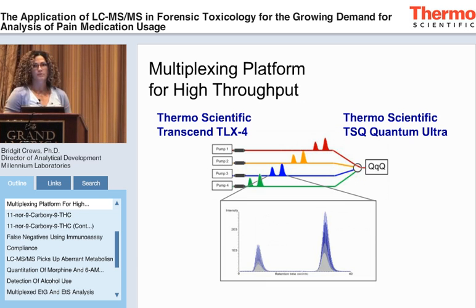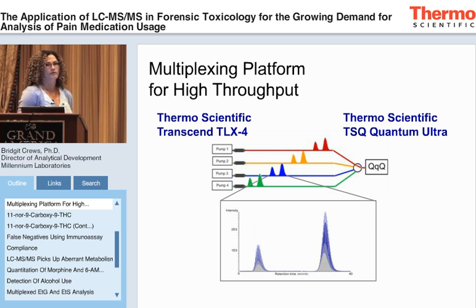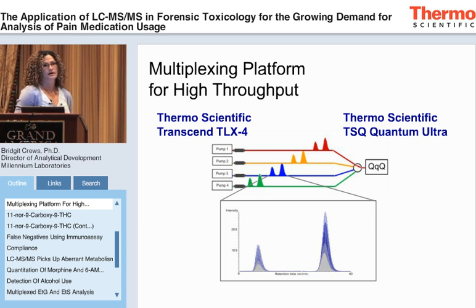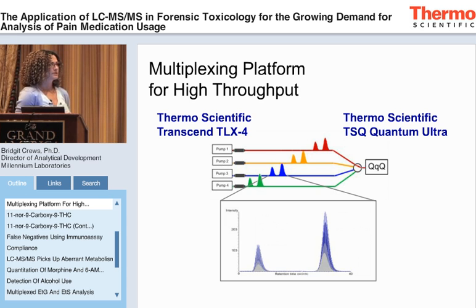In addition to simple sample prep, we need the fastest mass spec method we can run, and we're achieving that with a multiplexing platform. This is the Transcend TLX-4 system, where we have the ARIA multiplexing LC on the front and the TSQ Quantum Ultra triple quad as our detector. We have four pumps and four channels — we offset our LC runs to maximize detector efficiency. You don't have to wait for your sample to elute or while washing and re-equilibrating your column, achieving about a 40-second run time.